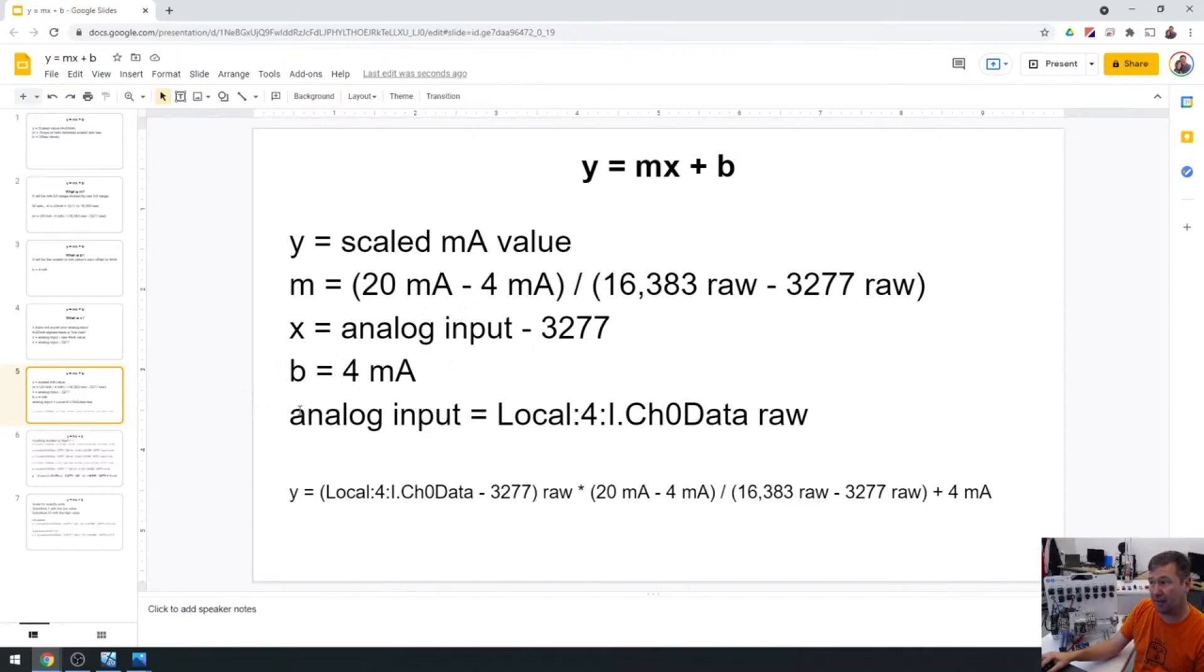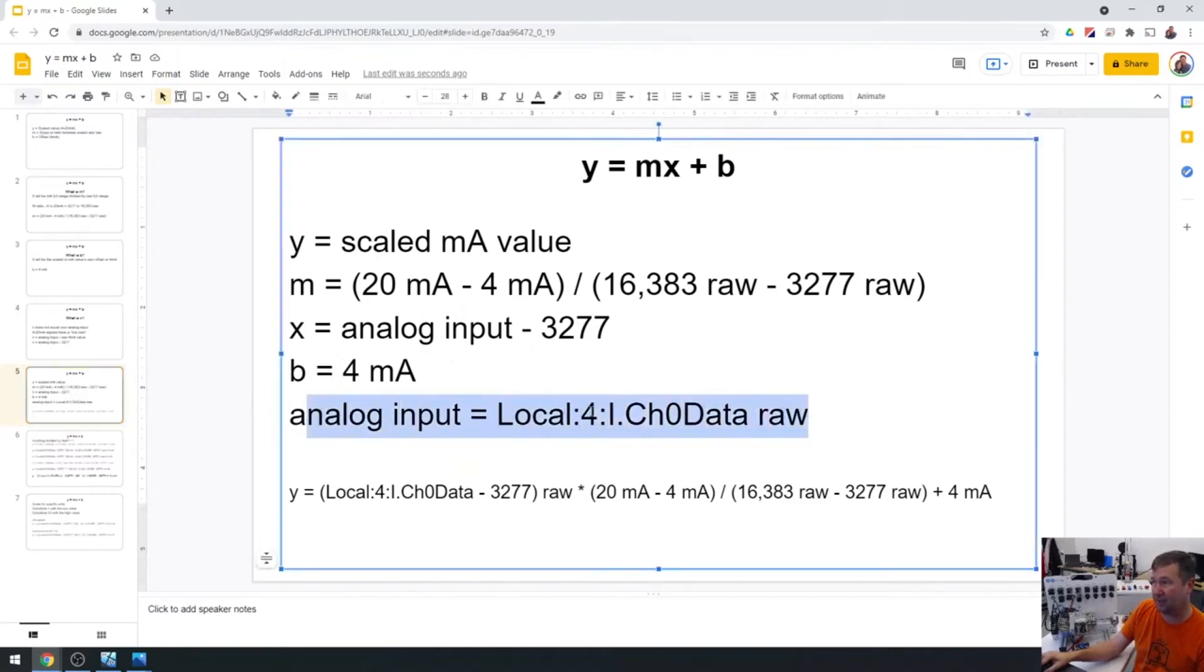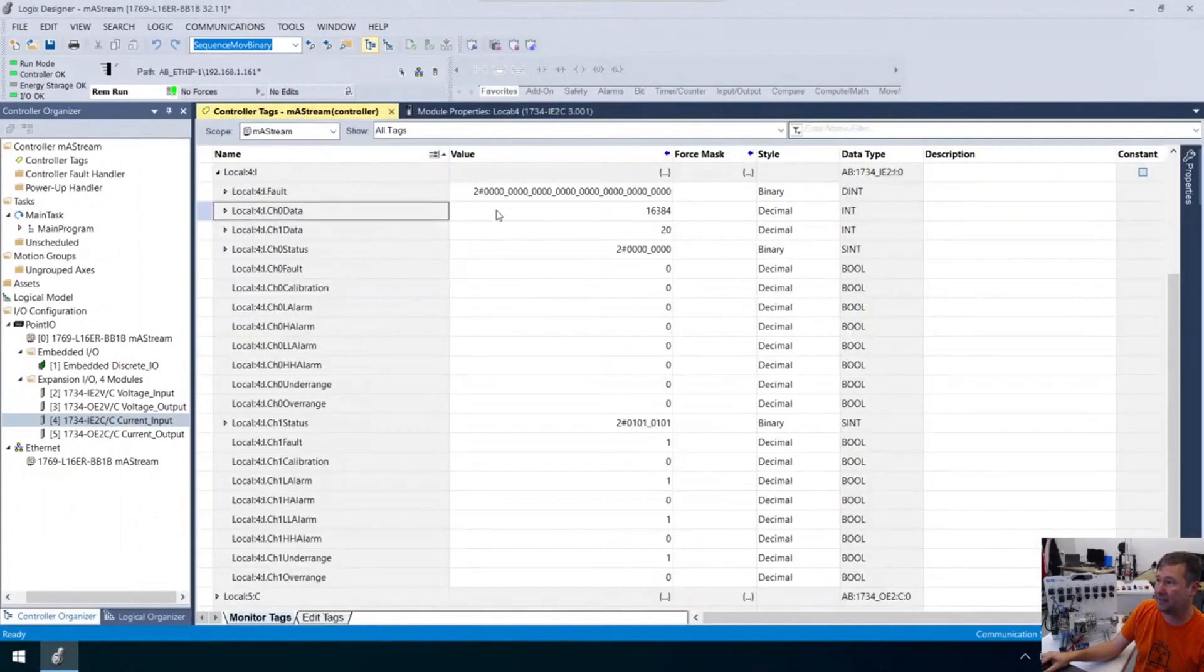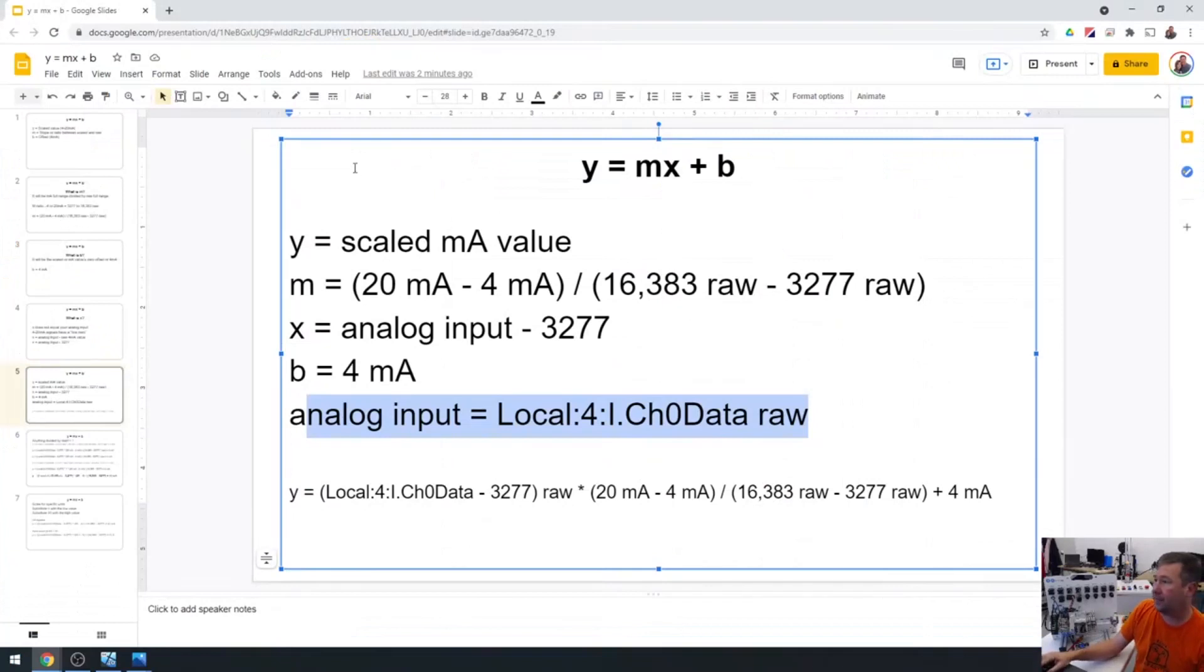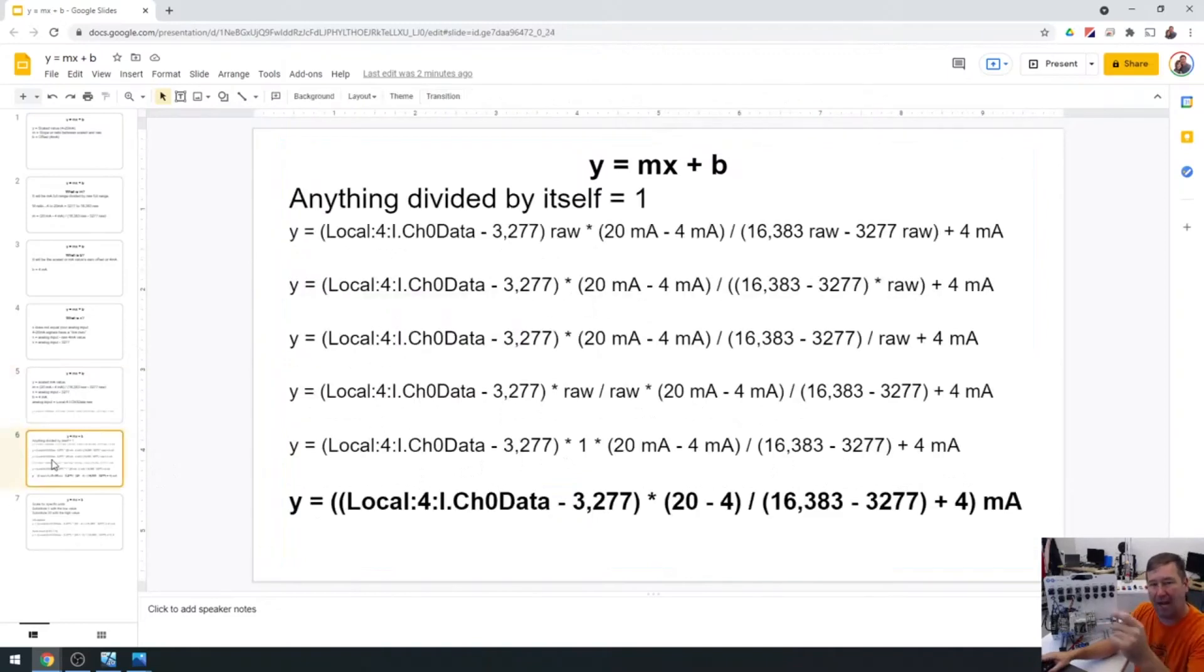Now the X is going to be the analog input minus 3277. Now what is the analog input right here? That's where this is going to come in. Our analog input is that local colon four colon I channel zero. Let's make sure we see that is what we found our value going at right here. So with all that, that means that Y equals the local colon four colon I channel zero minus that 3277 to get rid of that live zero.